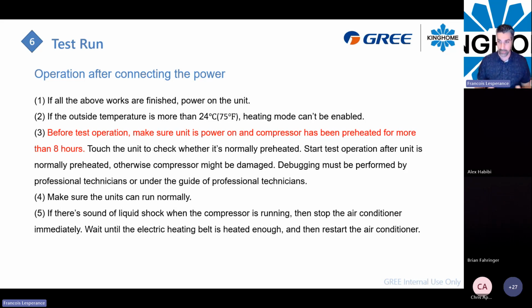But in cold weather, when it's very cold outside, you need to apply power to avoid liquid returning to the compressor, or making the oil too sticky and just breaking that compressor. So just make sure the compressor is warm when you start it.